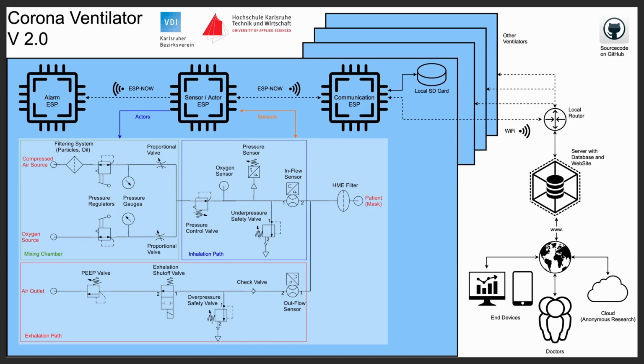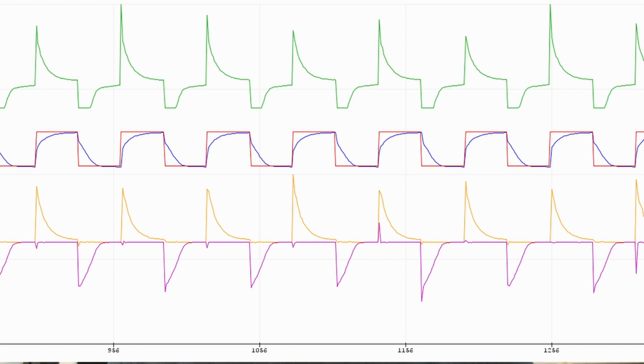Visualization and control. All the sensor data is collected by the sensor actuator ESP and is sent to the communication ESP via ESP-Now. This controller takes over the communication to the server. There the data is assigned to the patient and stored in a database. When the doctors call the website, they can log into their patients and display the live ventilation curves or change respiration parameters. Later, they will be also able to get alarm notifications and visualize previous respiration data from the database.